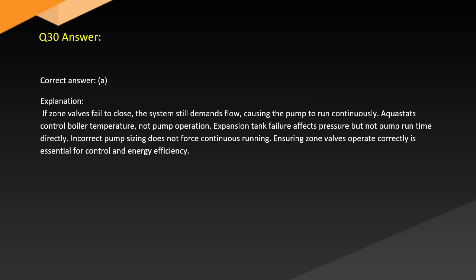Answer. Correct answer, A. Explanation. If zone valves fail to close, the system still demands flow, causing the pump to run continuously. Aquastats control boiler temperature, not pump operation. Expansion tank failure affects pressure but not pump run time directly. Incorrect pump sizing does not force continuous running. Ensuring zone valves operate correctly is essential for control and energy efficiency.